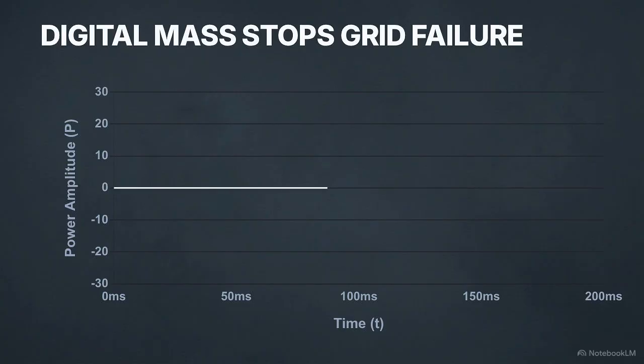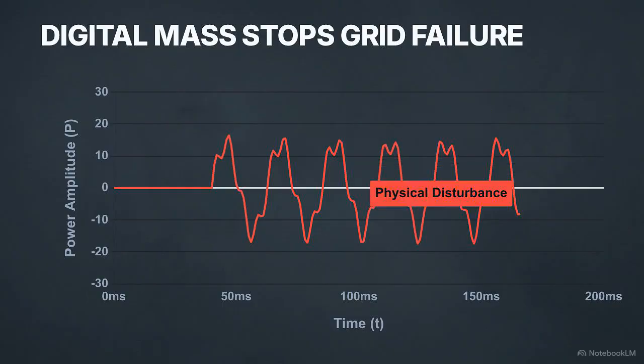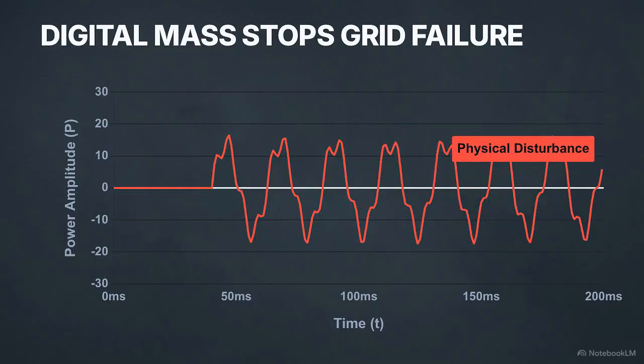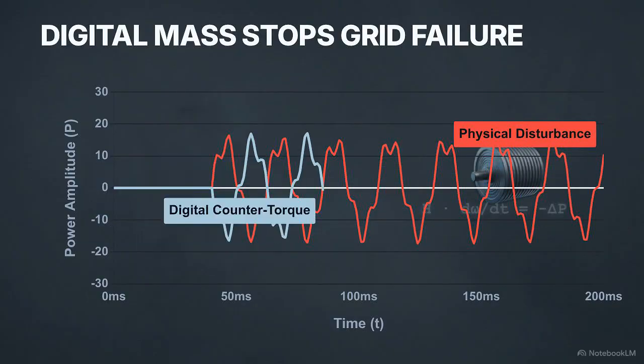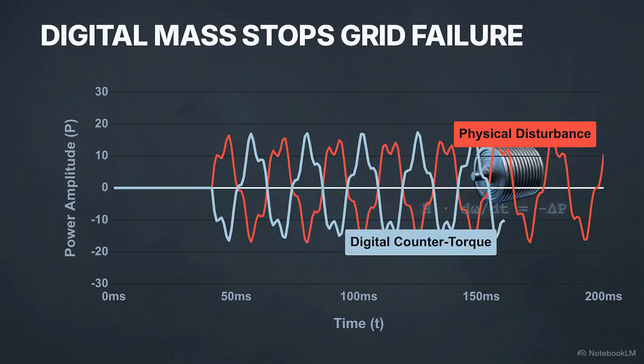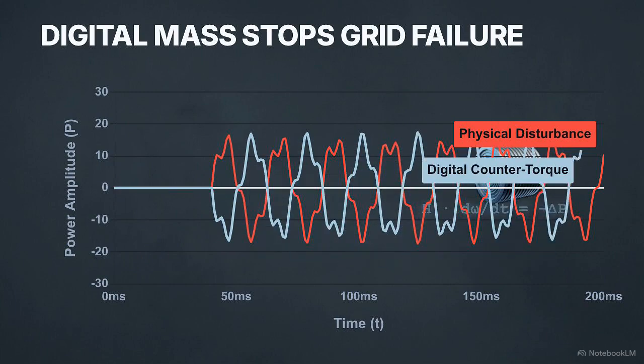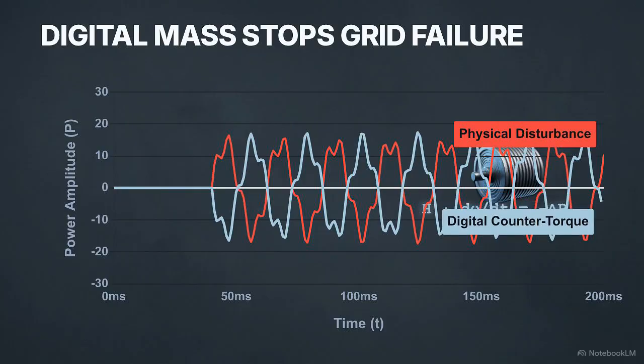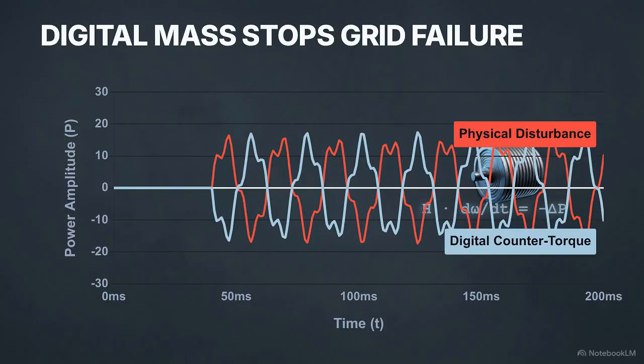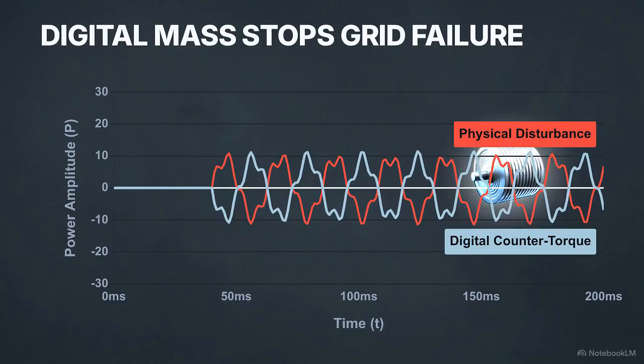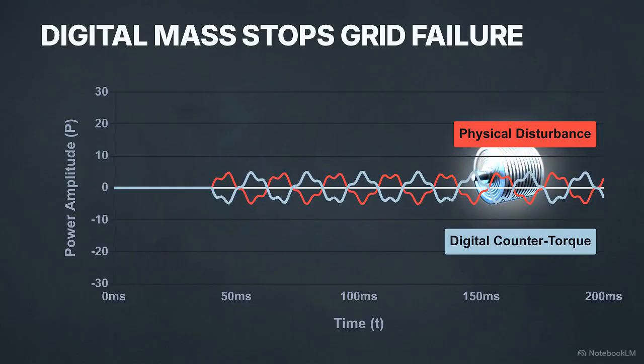This graph illustrates exactly how it works. A standard inverter outputs a wildly oscillating wave during a disturbance. A virtual synchronous generator calculates the exact physical weight and swing resistance of the old iron turbines, digitally injecting a counter-torque to oppose instability. By mimicking a heavy spinning mass, this digital illusion cancels out dangerous oscillations before they break physical hardware.